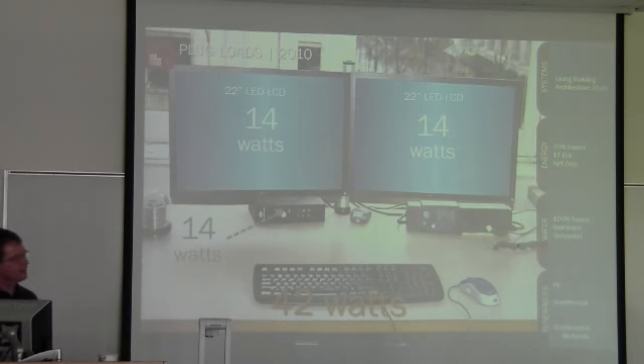And the latest thing, we just got a monitor in our office now. These are two 22-inch monitors. Now you can get single 27-inch monitors that give you the same viewable screen area as the 22s, and it does it with one monitor. So we're able to go from the 28 watts here down to, I think, around 15 watts total for the one monitor. So we're really pushing this down, and we buy the little kilowatt power strips, and we've done an actual full M&V system on our floor to look at HVAC loads, lighting loads, and plug loads separately. As we make these changes and sweep them out through the office, we can see the whole floor come down in usage, and we have that monitored over about a 3-year period now. We show that to our owners and advocate, okay, you're going to be in a net zero building, you can live in this environment because here's a system that you can create that's under budget.